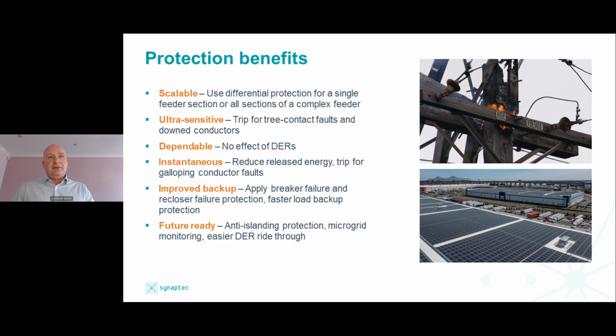So what we're talking about here are some of the more widespread benefits. Some of them apply at both distribution and transmission levels, but really using these distributed measurements, as we've shown here, does throw open opportunities for distributed, scalable differential protection with a greater or lesser amount of granularity. It also allows you to do other things, perhaps comparing currents and seeing how currents are dropping off, perhaps even doing directional comparisons as opposed to just magnitude and/or magnitude and phase.